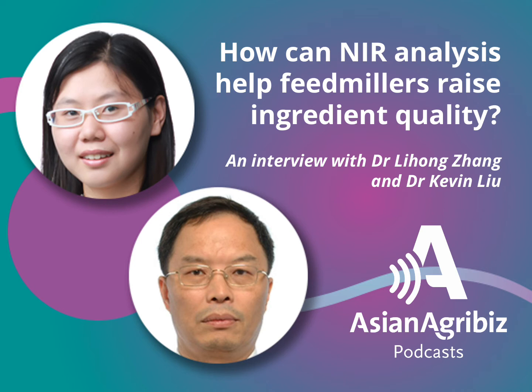Once a feed mill has reliable and robust calibrations, NIR systems can simply replace most routine wet chemistry analysis. Moreover, with the speedy results, feed mills can take control of ingredient quality, formulate diets on true values, and monitor the quality of outgoing feeds, which saves cost in a big way. NIR is an analytical instrument plus software. It does not require chemical reagents. Its maintenance is easy and not required frequently.